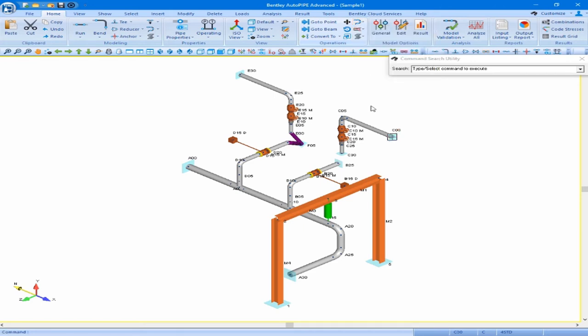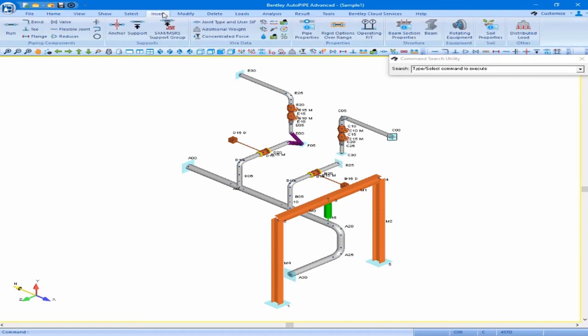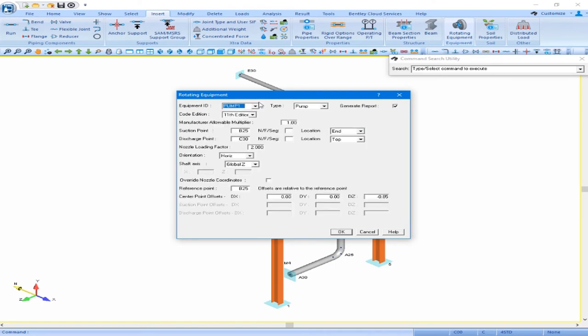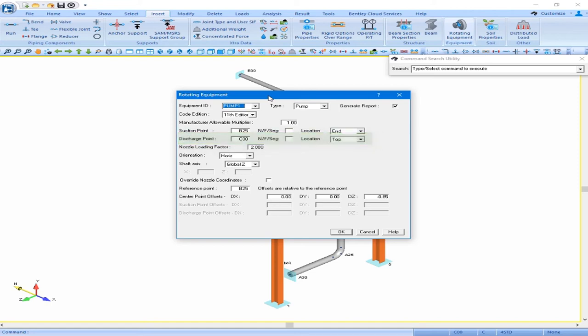We now see that on segment C the points are going in the opposite direction. We can verify that AutoPipe appropriately applied the segment reversal to the pump discharge point on segment C by opening up our rotating equipment dialog box — coming to the insert ribbon and clicking on rotating equipment. Reviewing pump one, we see that the discharge point, while initially inputted as C00, has been automatically updated to point C30 when we reversed the order of that segment. We can accept this dialog box by clicking OK.